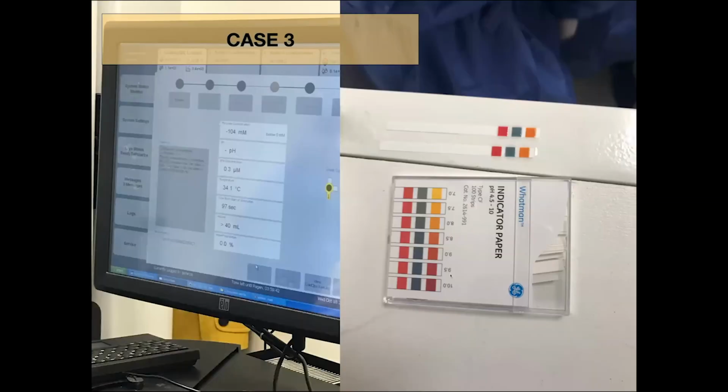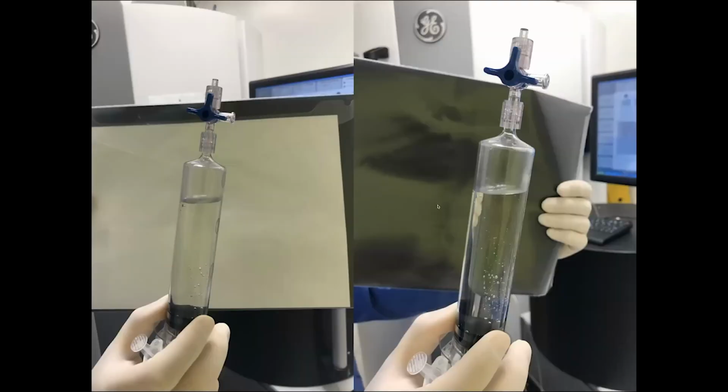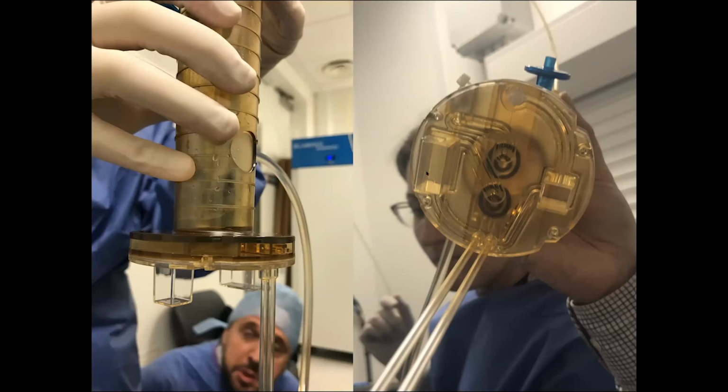Joint failure. Here's the third case. And actually, if you look very carefully, there is no real pH reading here. The solution looks really, really nice, ready to inject, but the errors are all over the place. And why is that? It's because the various valves in this technology didn't open. And you can see how we've gone from a happy team photo to a very sad face. This guy's about to cry. Everyone's really unhappy by this time.